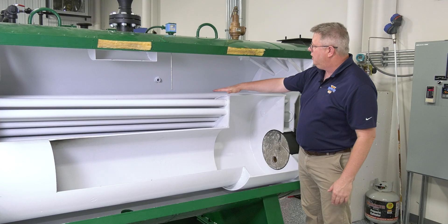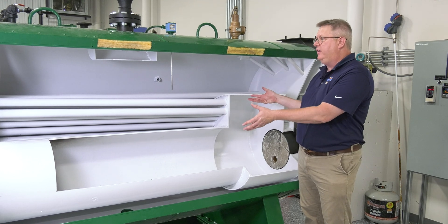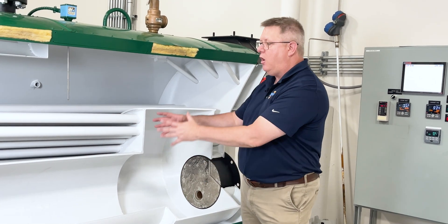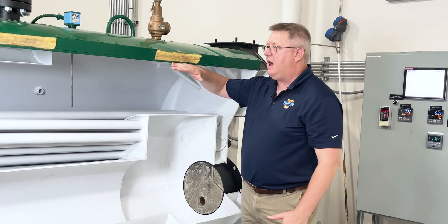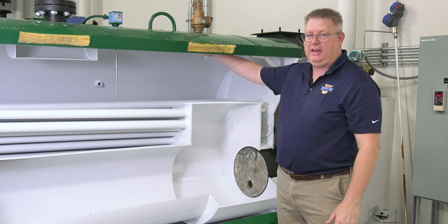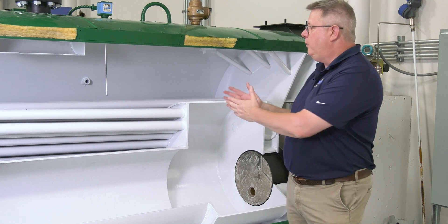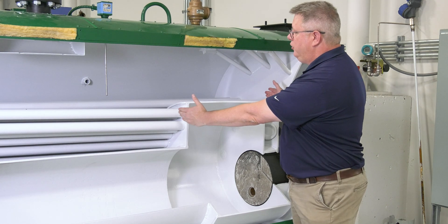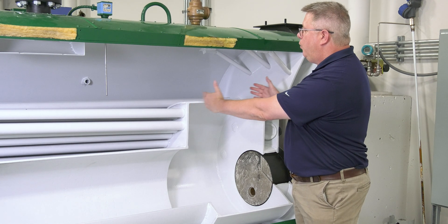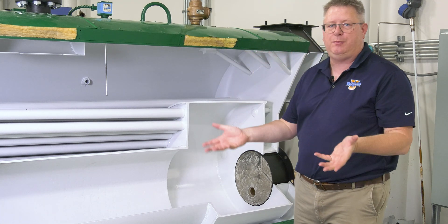But on a steam boiler, we may have a water level that's here. So as we're warming it up and we're at 140 degrees, the tubes and furnace are all at 140 degrees, but the top of the vessel may not be. It may still be nearly at ambient temperature because there's air in here if we're not generating steam, and that air insulates. So we will have pushing and pulling of tubes, where the water is warming up against the relatively shorter shell because it's not expanded yet.